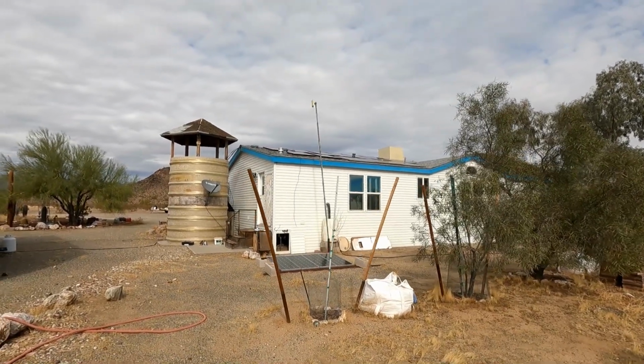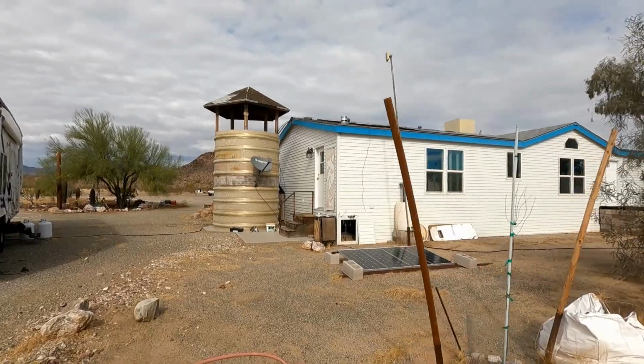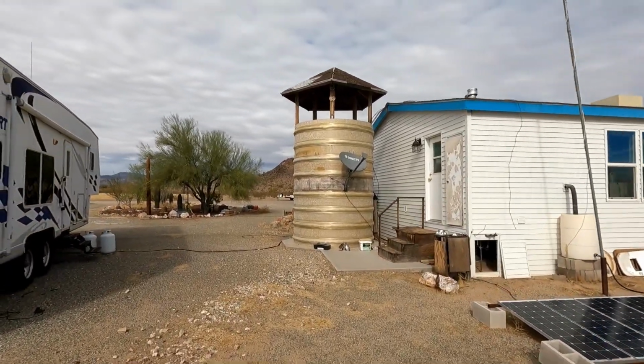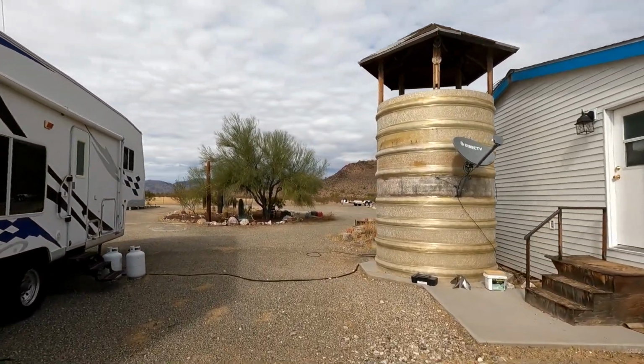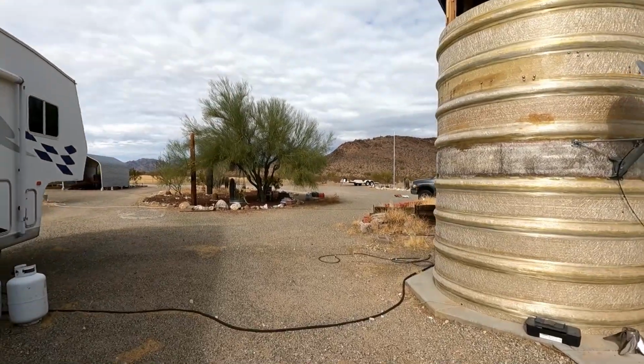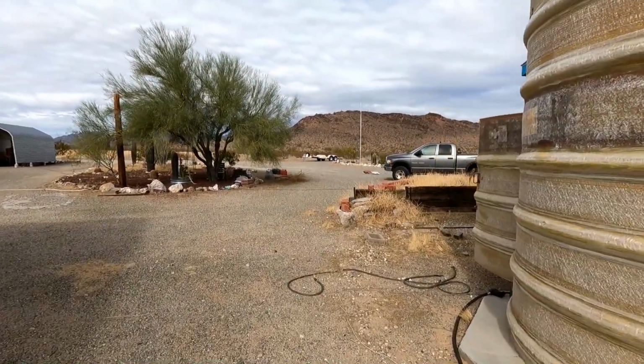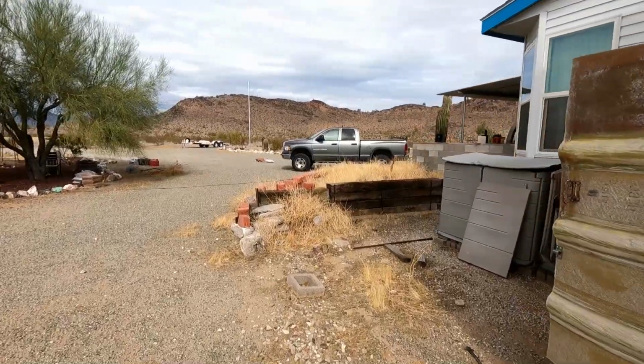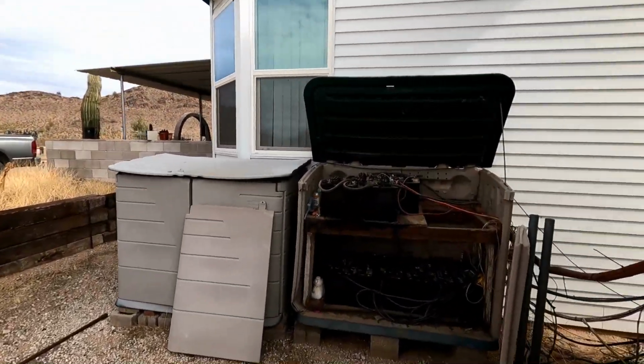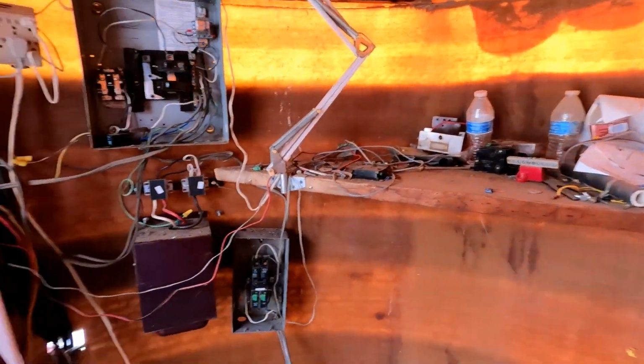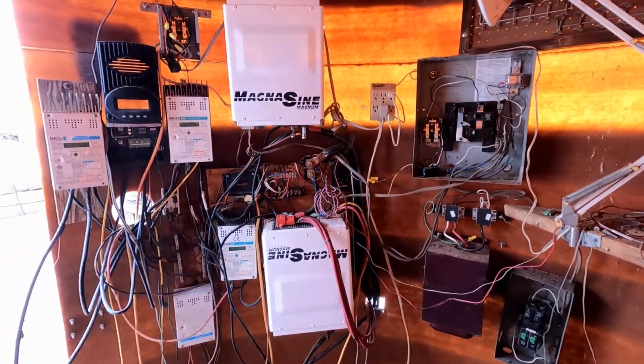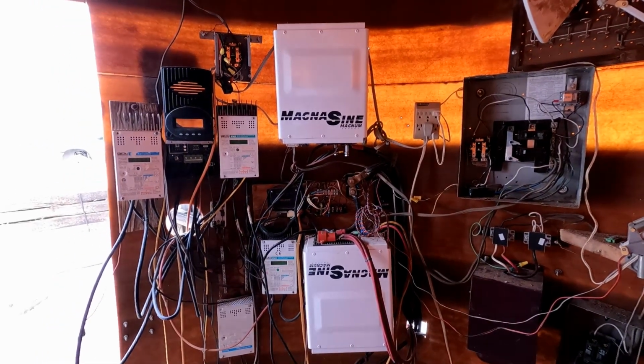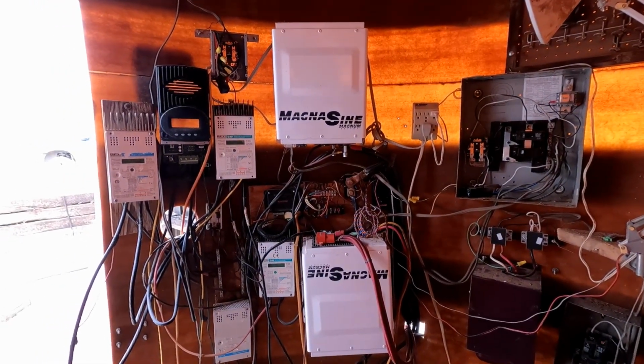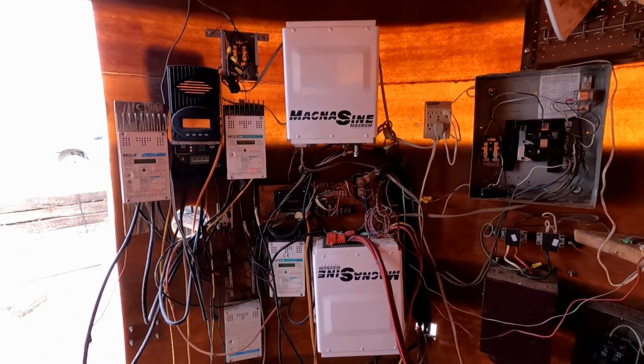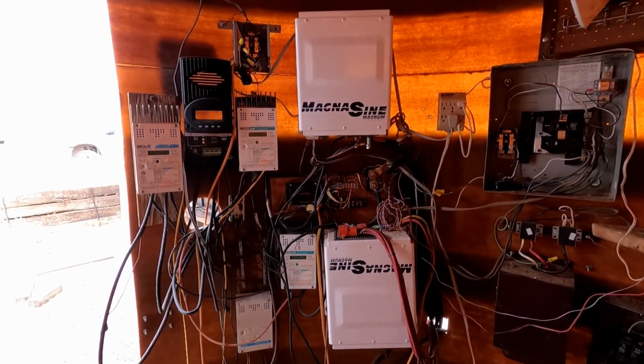Having a backup generator on an off-grid solar power system has a lot of advantages. When you're not getting enough solar power, if you need a backup source of AC because of some problem in the solar power system, there's a lot of desirable reasons for having a generator for backup power. Something to consider when you're adding that for backup power to a system such as this, which has automatic controls, is that the inverters have now become automatic transfer switches.